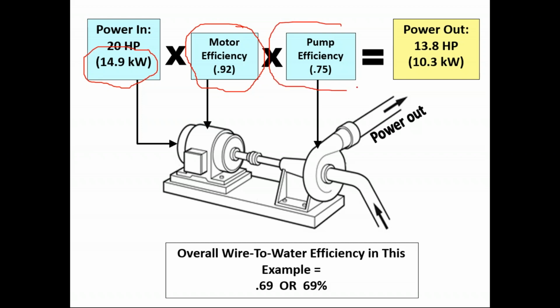Take that result and multiply it by the pump efficiency. Now, most pumps that we see out in the field are not delivering 75% efficiency, but we will use that in this example. So what we actually get on the discharge side of the pump in terms of useful work is only 10.3 kilowatts versus the 14.9 kilowatts that we paid for. So the overall wire-to-water efficiency in this example is 69%. And what that means in dollars and cents is, for every dollar you spend on energy, you get 69 cents worth of useful work. And that, incidentally, is one of the lowest margins of efficiency of any industrial use of electricity in the world, actually. And again, it's just because of the laws of physics.